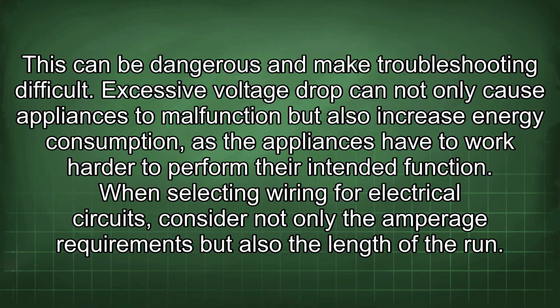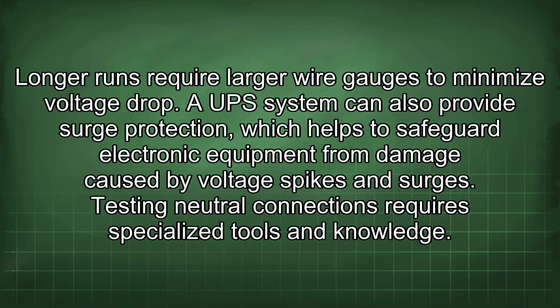This can be dangerous and make troubleshooting difficult. Excessive voltage drop can not only cause appliances to malfunction but also increase energy consumption, as the appliances have to work harder to perform their intended function. When selecting wiring for electrical circuits, consider not only the amperage requirements but also the length of the run. Longer runs require larger wire gauges to minimize voltage drop.